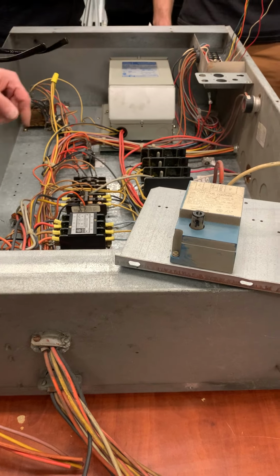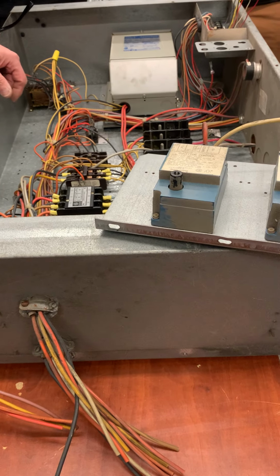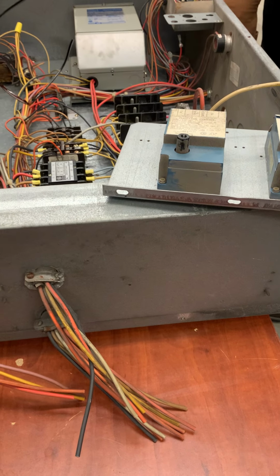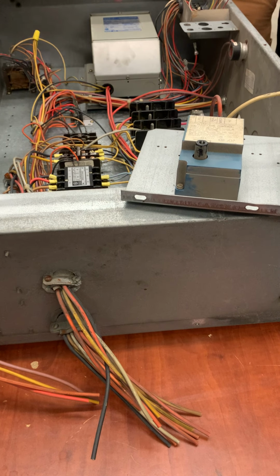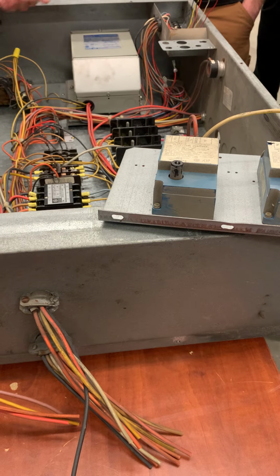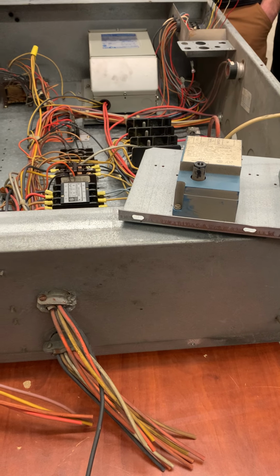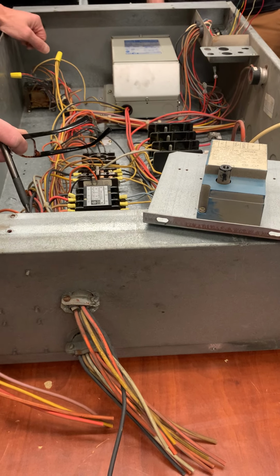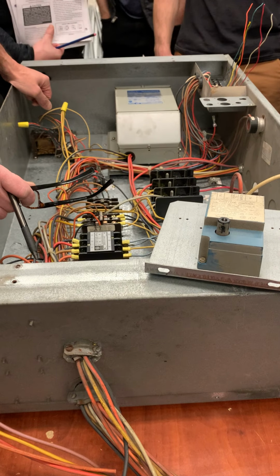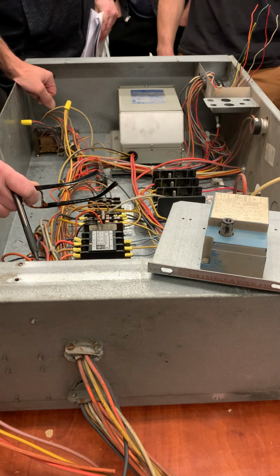As soon as you see a wire go through something like this, you know I'm sensing the current. As soon as you see the transformers, you know what's going on. As soon as you see small wire going into a big unit, you know it's 600 volts. You see 2 ignition controllers, you know you got 2 gas valves. You see W1, W2, you got 2 stages of heat. Y1, Y2, 2 stages of cooling. See how easy it is to pick up so much information by what you know.